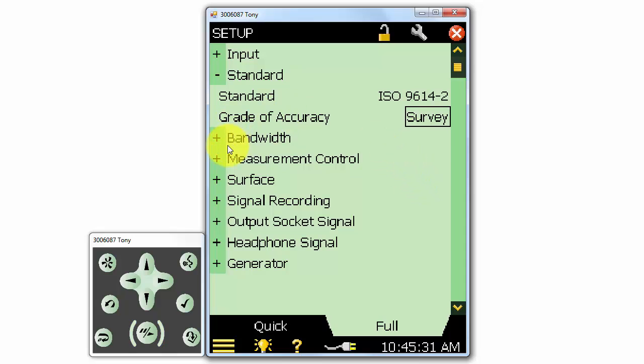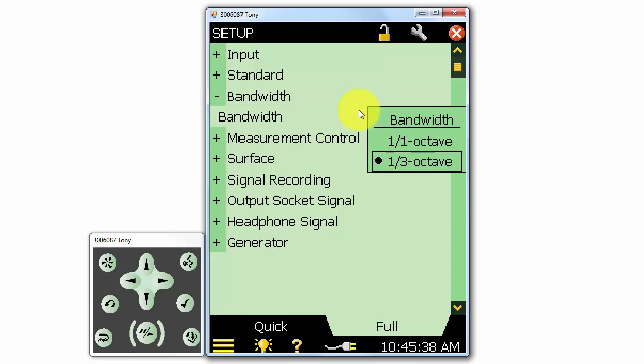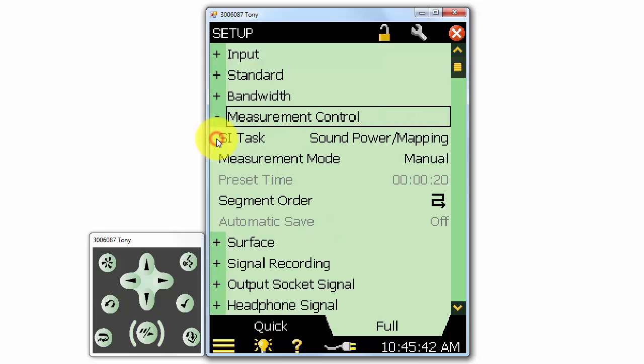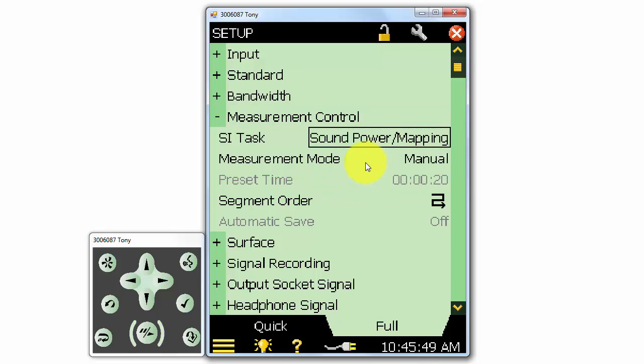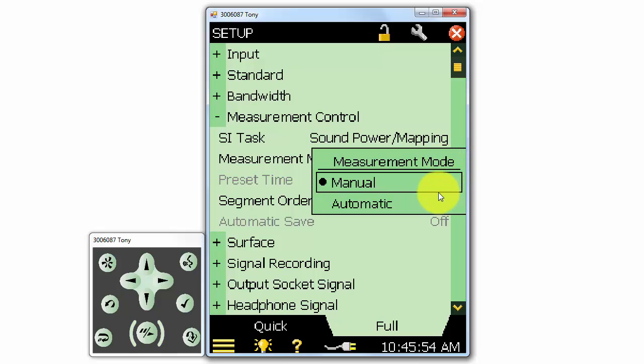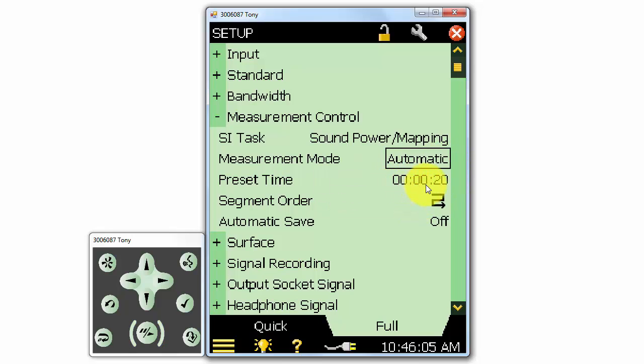Next, we can specify the bandwidth of the measurement. Third octave measurements are most common. Under measurement control, we can also select the sound intensity task as we did before on the main screen. Like other applications on the meter, we can select manual or automatic mode to control the duration of the measurement with the start and stop button, or to automatically stop after a predefined time. The ISO 9614-2 standard requires at least 20 seconds per measurement.